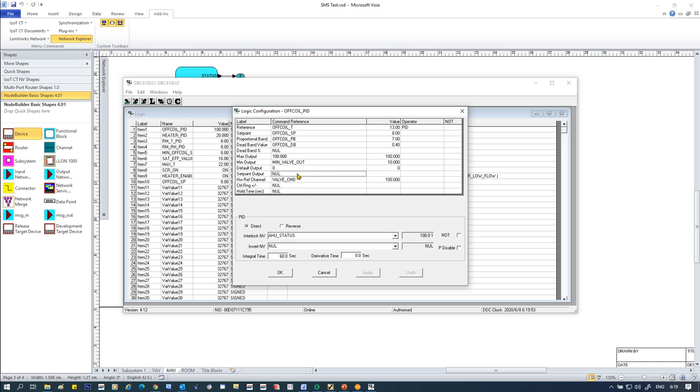Okay. Here is the set point output value. For coil temperature usually you cannot use a set point output, because the set point usually will be changed. If you control both RH and T, the set point cannot be fixed at one set point, it will be changed. So usually don't have a set point output value, so you leave it.